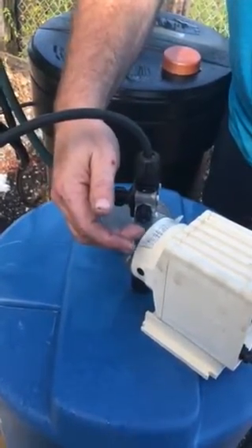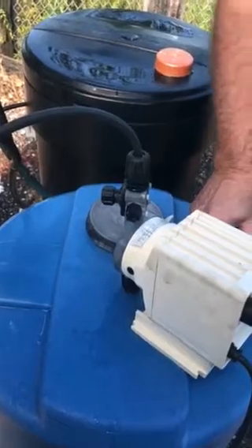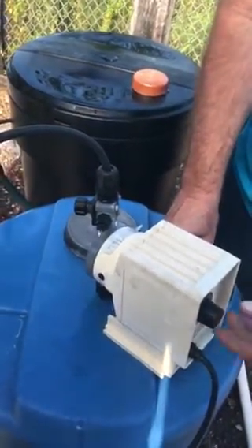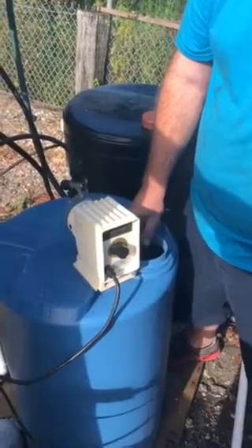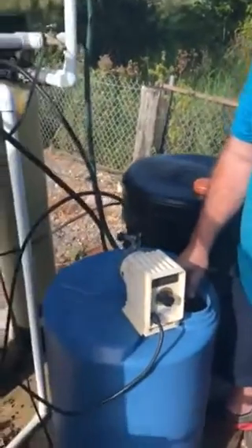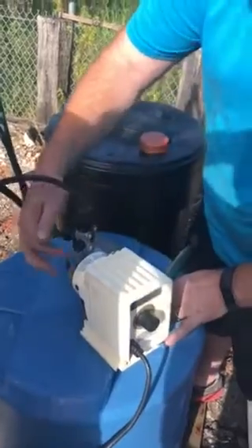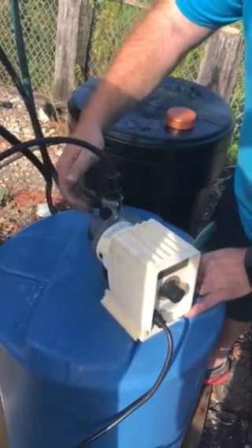You're going to see how it's spitting air and all that out, because this has definitely run out of chlorine. Now you can see it's kind of coming out a little bit. When I'm priming the pump, I always turn it up to 100%. But don't forget to turn it back down to where you have yours set — usually 50 to 60%. It's pumping pretty good now, a pretty decent stream. Good pressure back. I'm going to turn it back the way it came.